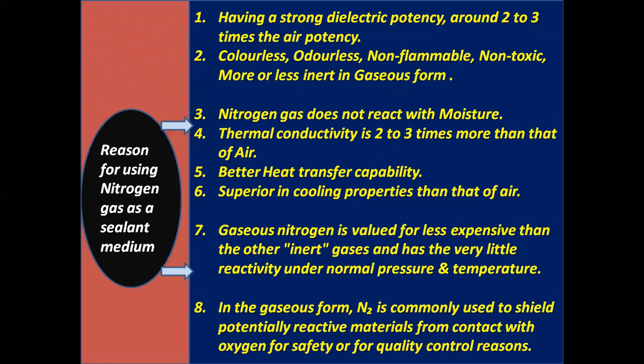Now, the reasons for using nitrogen gas as a sealant medium. Number one, having a strong dielectric potency around 2 to 3 times the air potency. Number two, colorless, odorless, non-flammable, non-toxic, more or less inert in gaseous form. Number three, nitrogen gas does not react with moisture. Number four, thermal conductivity is 2 to 3 times more than that of air. Number five, better heat transfer capability. Number six, superior cooling properties than that of air.